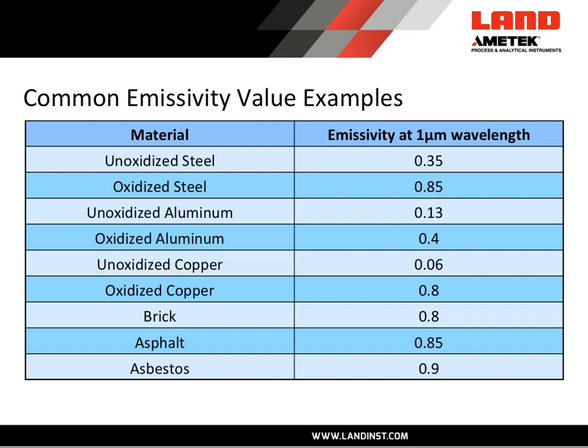The copper examples are quite interesting. Oxidized copper — think of copper that's dark and covered with verdigris — has a very high emissivity value of 0.8. However, if you clean that copper and polish it up, think of a shiny copper kettle, the emissivity value is much, much lower at 0.06 — only 6% of the energy is capable of being emitted from the surface.